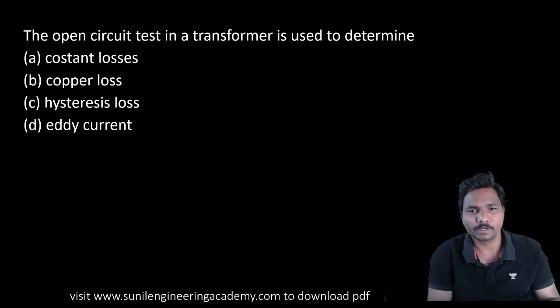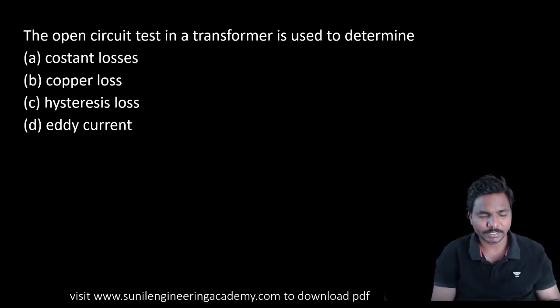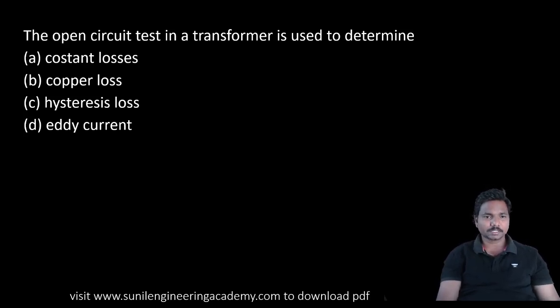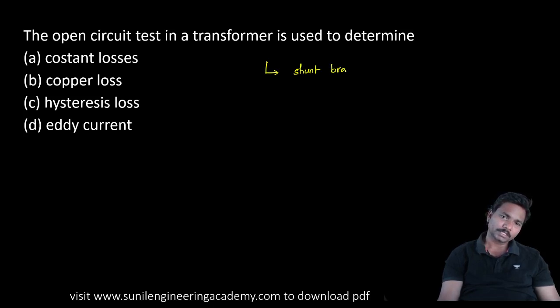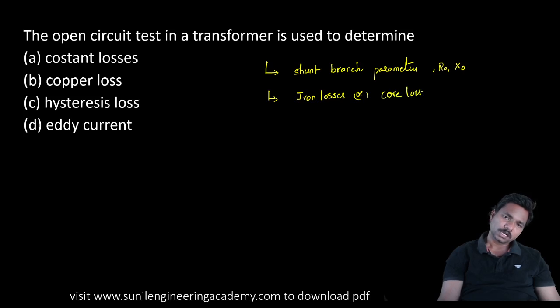Open circuit test in a transformer is used to determine dash: constant losses, copper losses, hysteresis loss, eddy current losses. So this open circuit test in a transformer is used to determine shunt branch parameters, that is R naught, X naught, and iron losses. These are also called core losses, and it is also used to separate iron losses into hysteresis and eddy current losses.